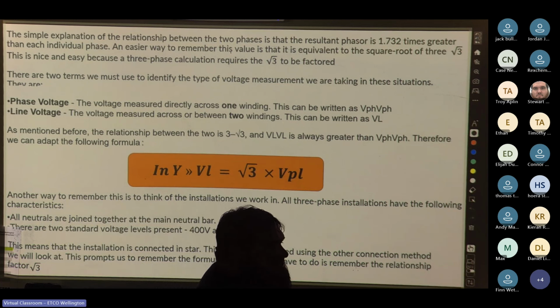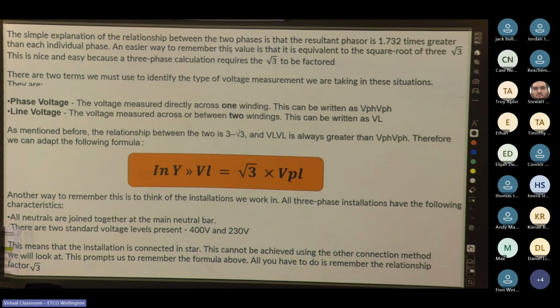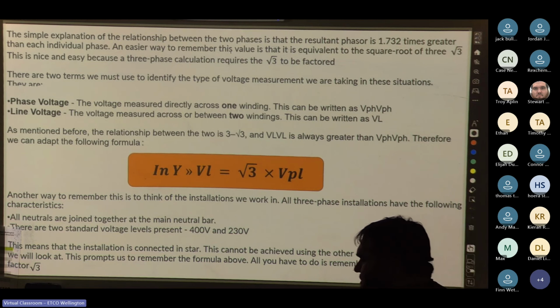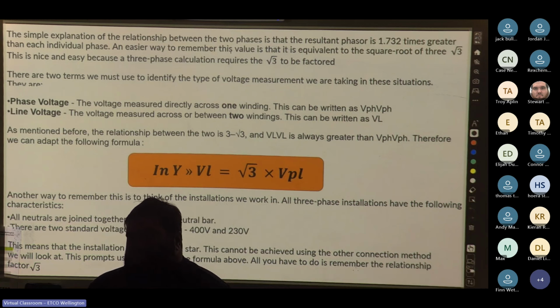Yes, if it was a delta installation or a delta connection, we would not have a neutral. So if you have a three-phase motor or a transformer connected in delta, you will see no neutral for that circuit. Obviously, in a factory, you'd run a neutral to a piece of machinery because maybe the machinery has some control gear that needs a neutral. So oftentimes you'll run three-phase to a control box with a neutral, and then tap off the neutral for the control circuitry, or sometimes you'll use two-phase 400-volt control. But in delta, no neutral.